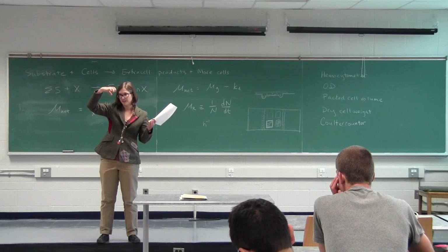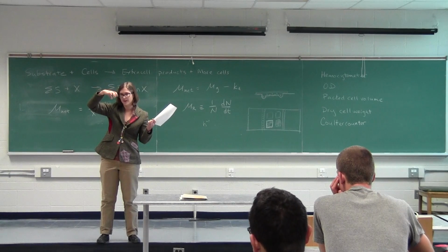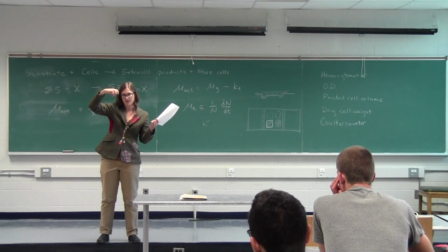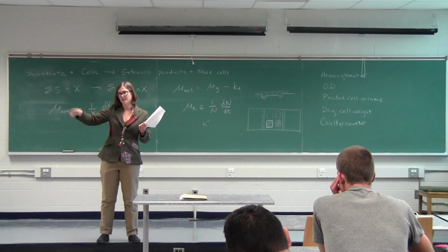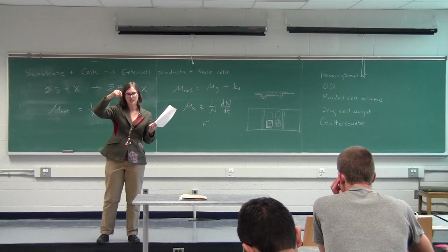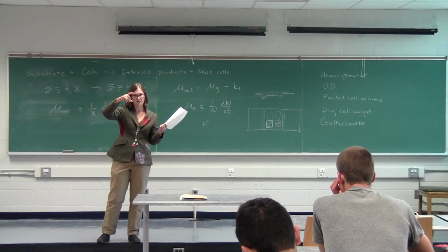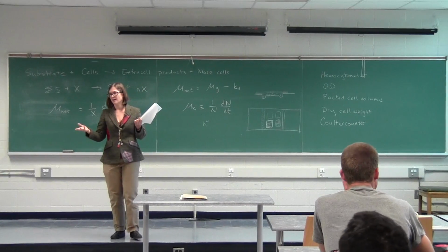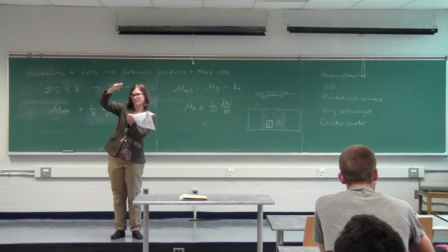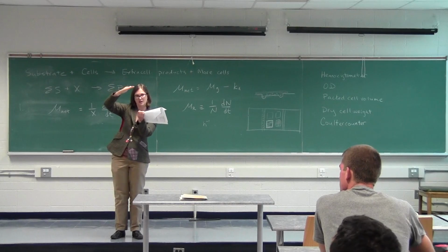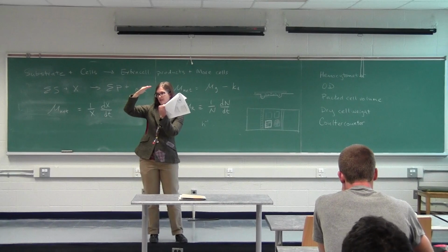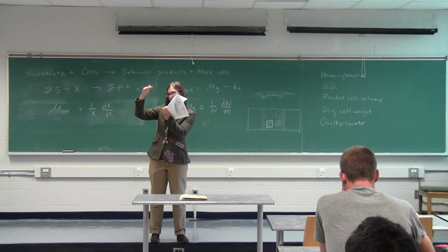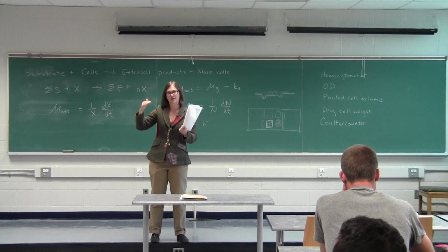Clear medium will have one electrical impedance, and a cell will have another. So it correlates an electrical impedance change of this much to a cell number. It very rapidly takes those cells up, counts how many interferences there are in the electrical impedance, and then, because it knows the flow rate and the period of time, it figures out what volume that's been, and can figure out cell concentration from that.